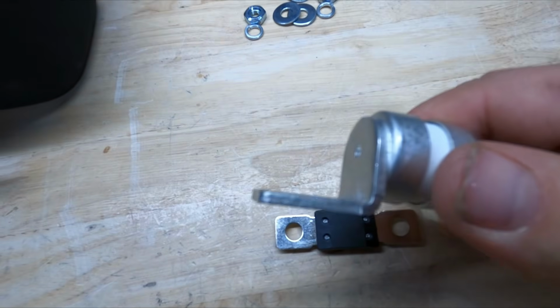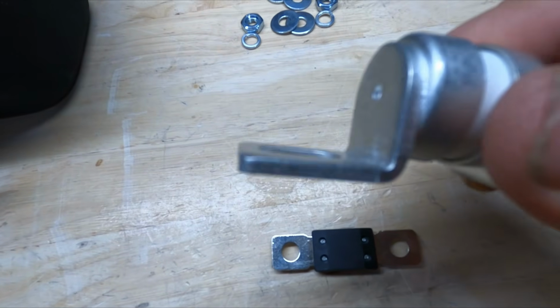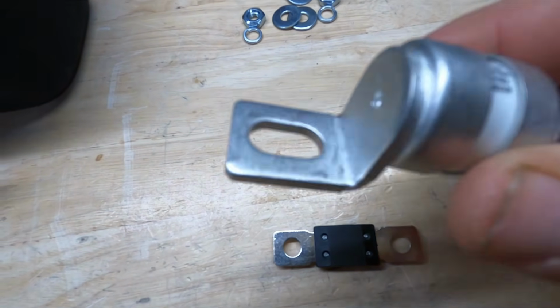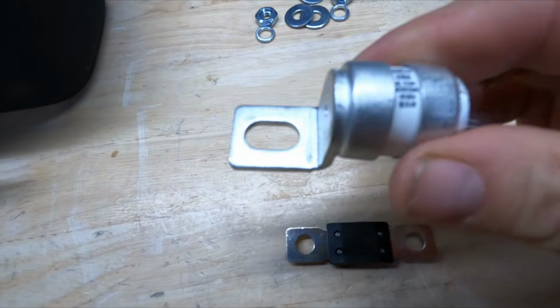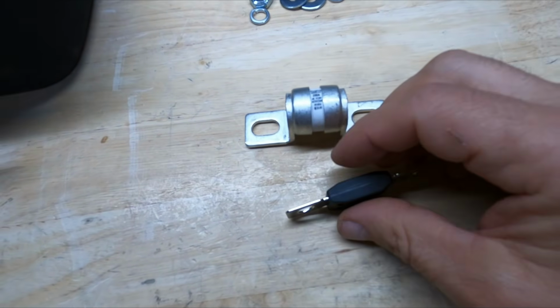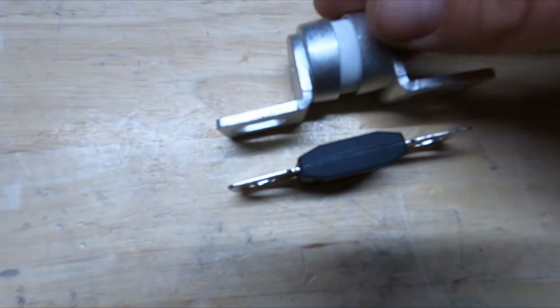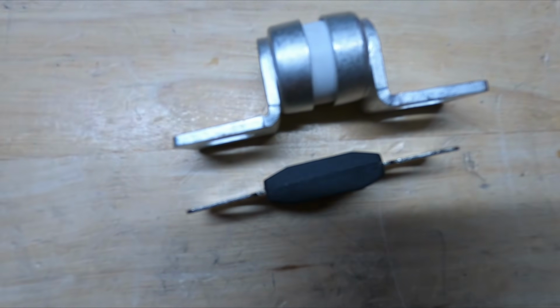If you look at a Class T fuse, look how thick that is. That can carry 200 amps continuous. And that's why we need to start seeing Class T fuses inside these batteries, especially the 12-volt batteries. This will give us a higher AIC value and help to mitigate heat.